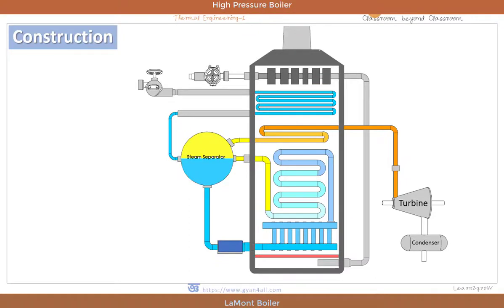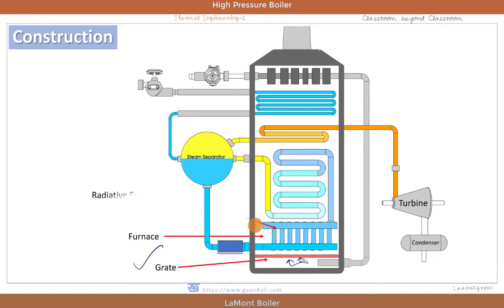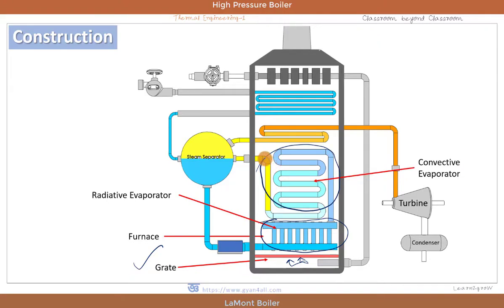Now let us understand the most important parts of the Lamont boiler. This is the grate on which the fuel is placed for burning, and the hot air is supplied from the bottom of the grate. This is the furnace where the fuel is burned and hot gas of combustion goes up and is dispersed to the atmosphere through the chimney. The first water tubes are the radiant evaporator, and next are the convective evaporator. Steam from the convective evaporator enters into the steam separating drum, which contains both water and steam. Water from the steam separating drum enters into the radiant evaporator through the circulating pump.